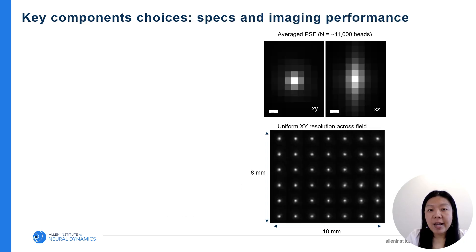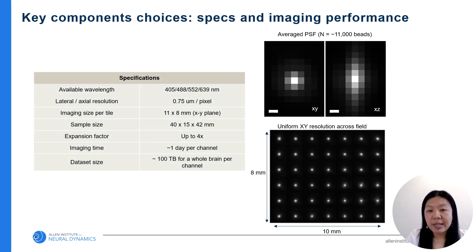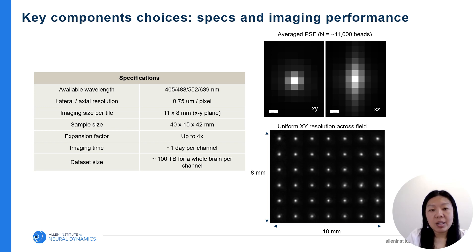This shows the point spread function in the X-Y plane and the X-Z plane. The X-Y resolution is uniform across the entire field of view. Here are the full specifications for the system: it offers four imaging channels, the sample size can be up to 40 by 15 by 42 millimeters, and to finish a whole brain scan with one wavelength, imaging time is about one day producing a dataset of about 100 terabytes.